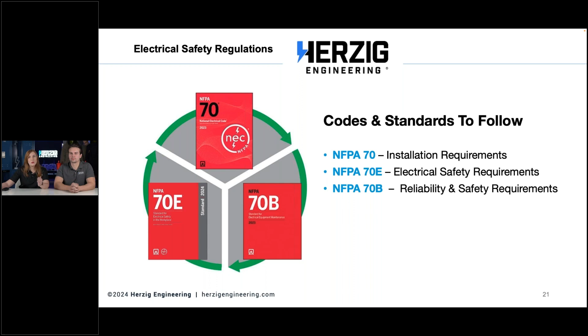Notice it doesn't say practical safe working area for qualified workers relative to the hazard, or electrical workers—it's everybody. So this applies to unqualified personnel as well. The employer needs an electrical safety program with documented safe work practices following NFPA 70E, and must provide training on those practices. Employees are supposed to listen and comply, since that's part of risk control and hazard awareness. Until all workers are aware of the hazard, they won't know what to do.